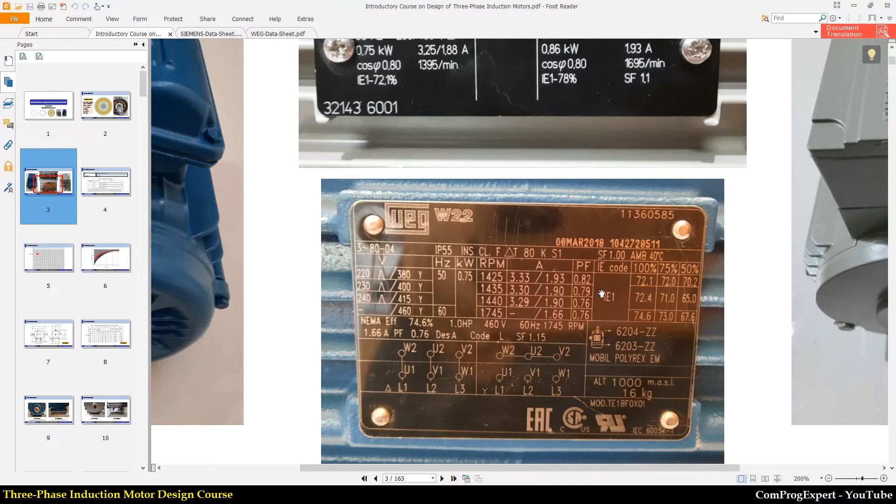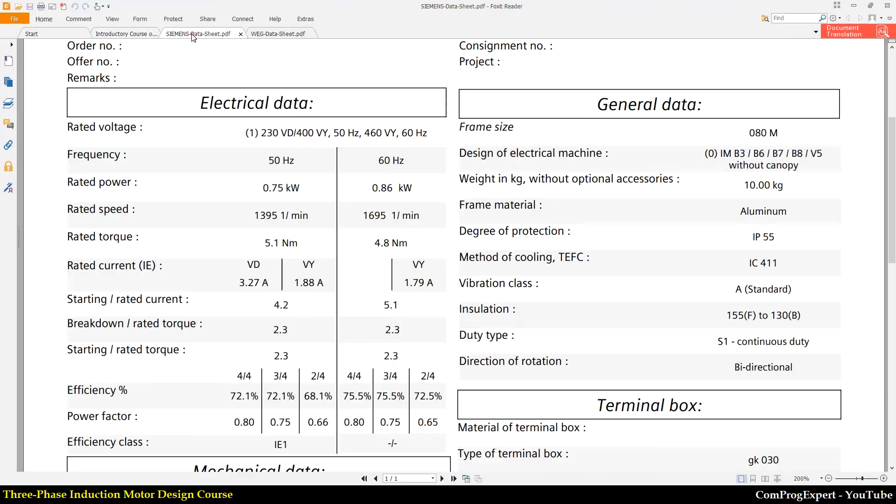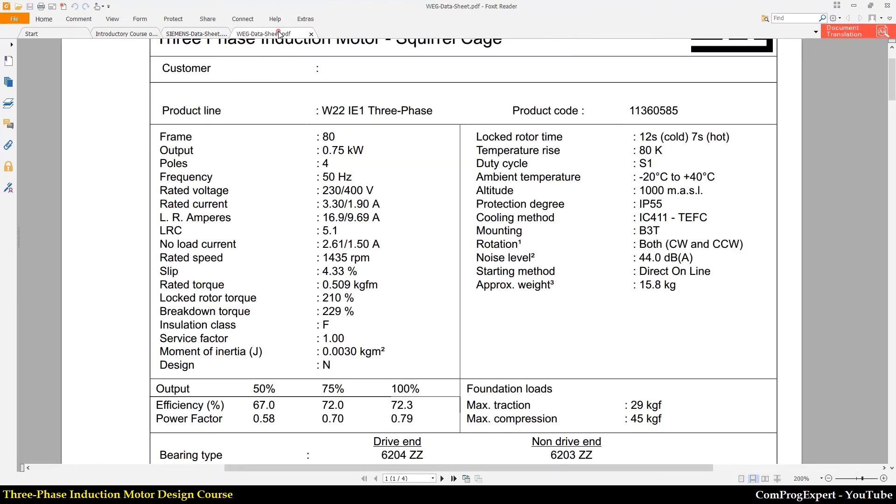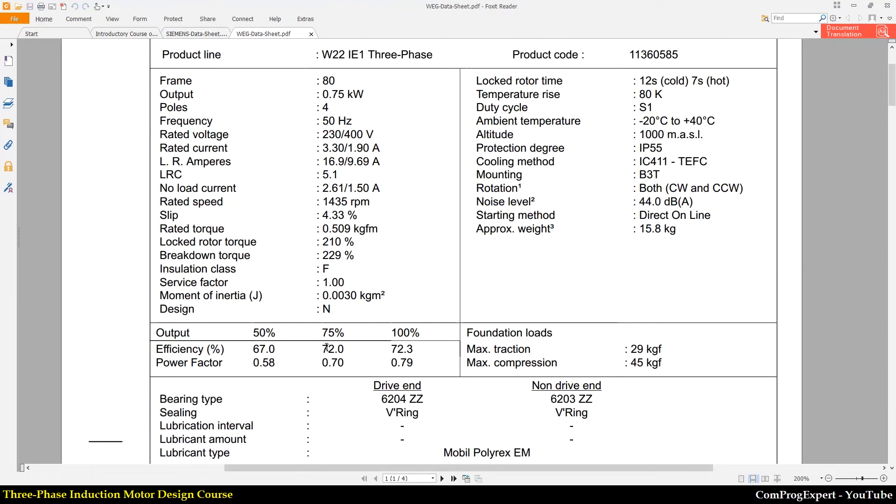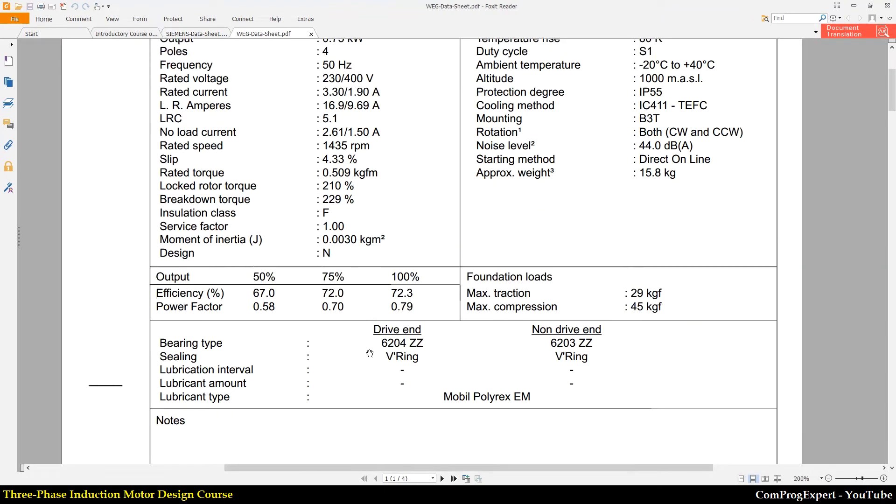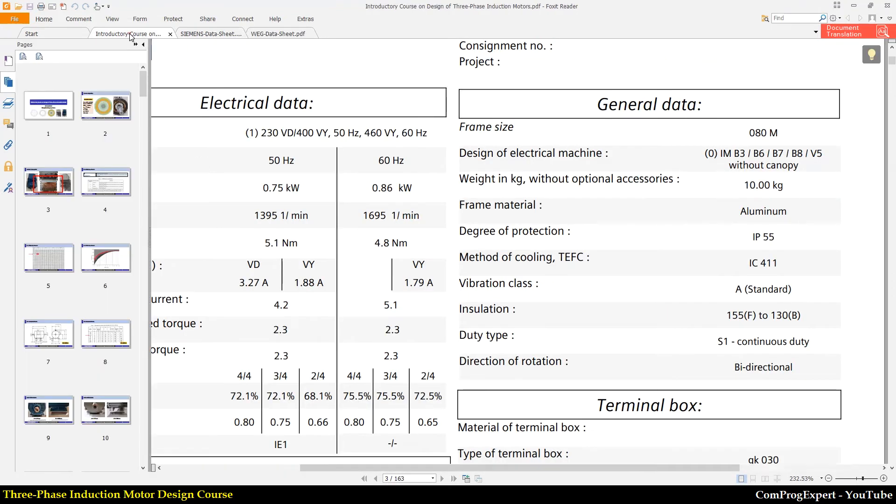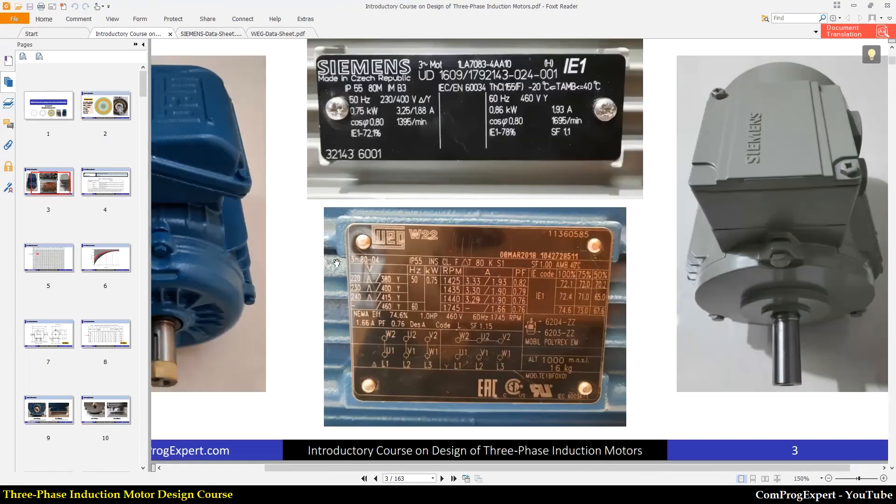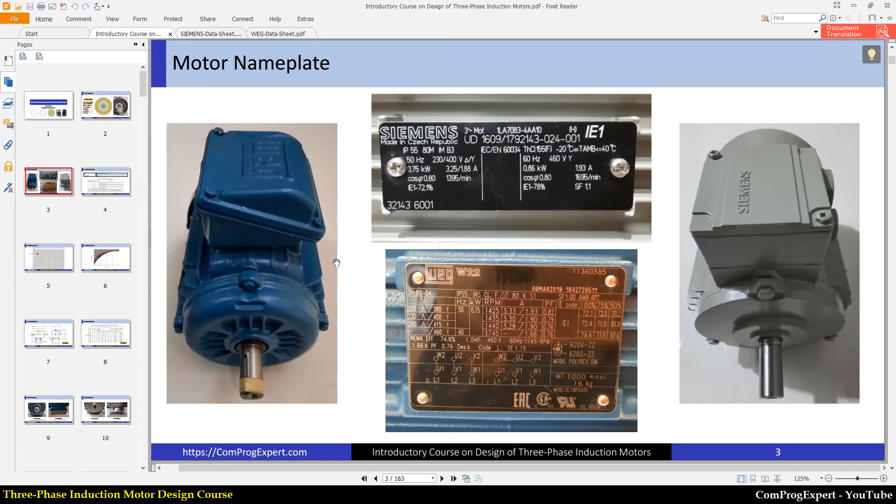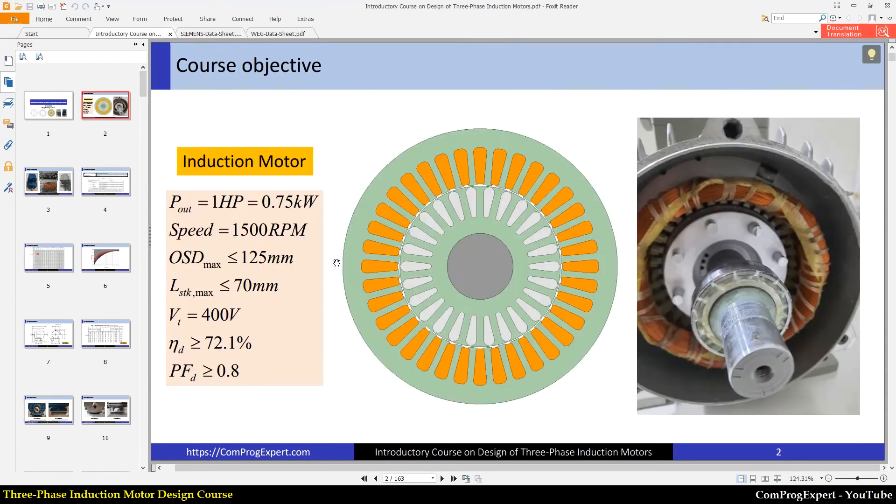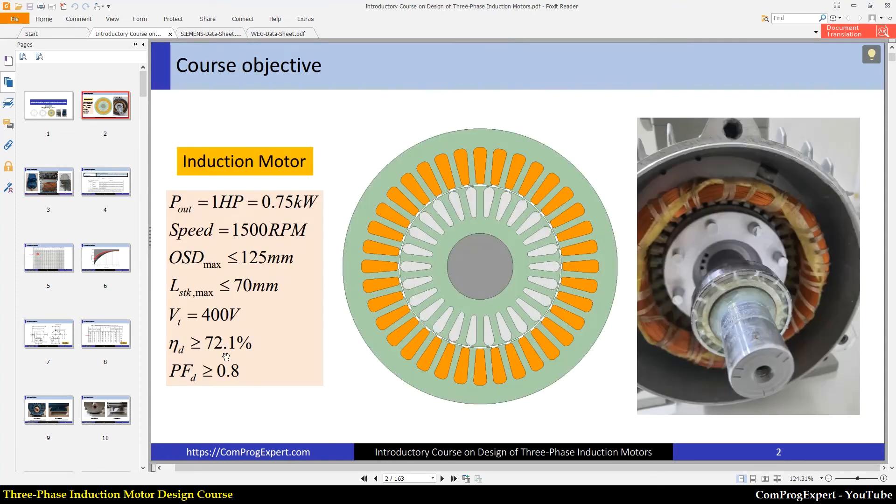And also the efficiency class for this motor is IE1. You can see the IE code. So the efficiency of the Siemens motor is 72.1%. This is the full load efficiency. You can see here. And also the full load efficiency here, 72.3. So the efficiency class is IE1. So also I consider IE1 here. The desired efficiency should be higher than or equal to 72.1%.